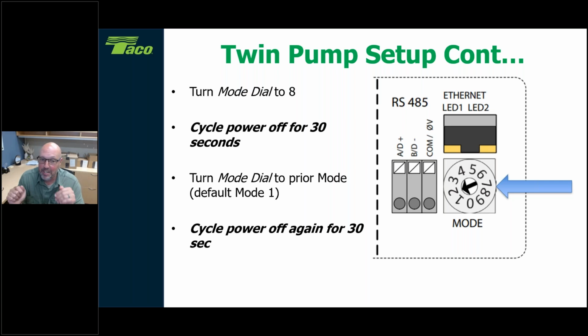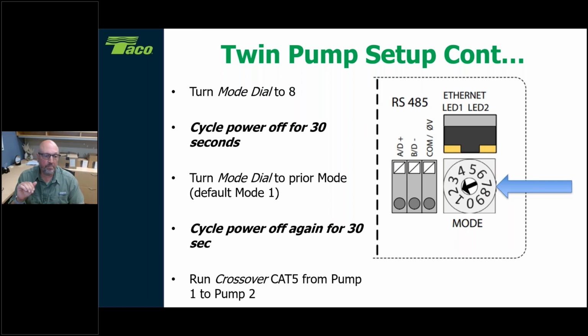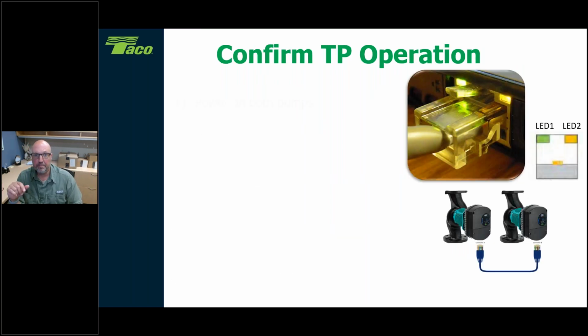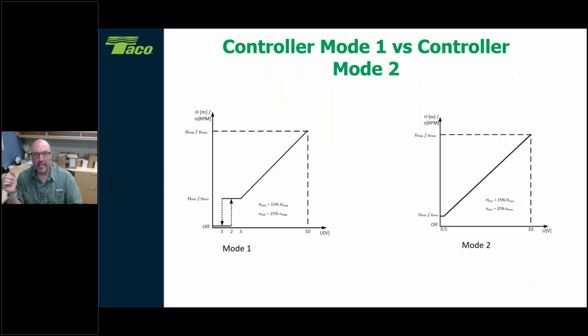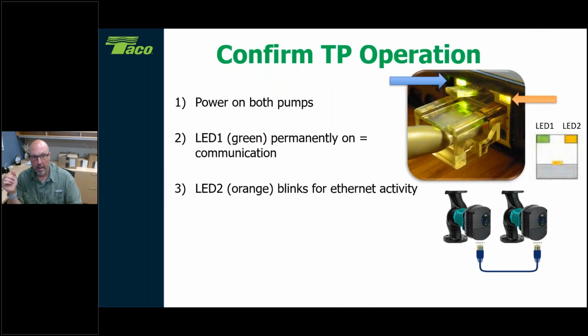Cycle the power down again for 30 seconds. Leave it in mode 1, and then you're good to go in the twin pump setup mode. So it has to go to 8, power down, turn it to 1, power down again. And then you're all set to go in twin pump mode. It does know to communicate between the 2 circulators. Okay, and then you run your Cat5. So, whoa, sorry about that. Went too far. I hit some buttons here.